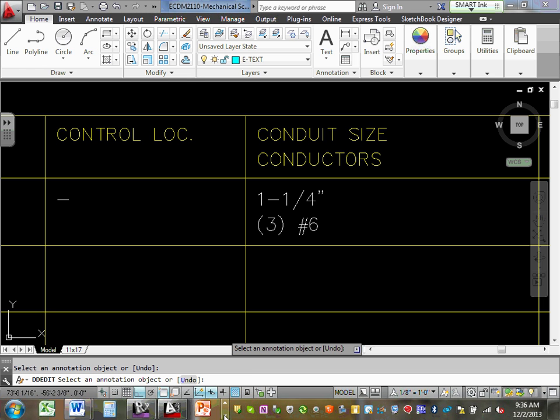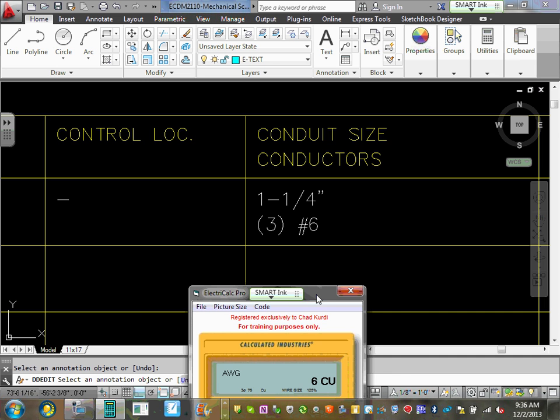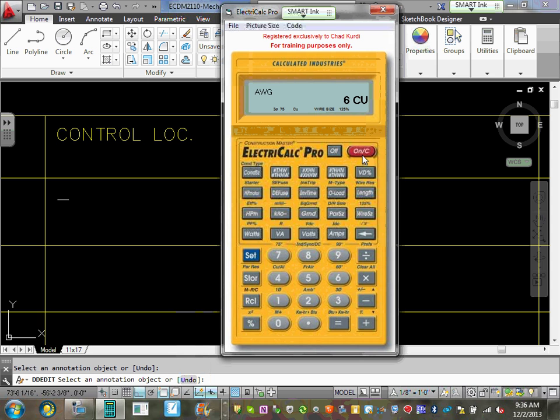Let me show you how to size the conduit. Either use the calculator, or you're going to go back to how we sized conduit before. Now remember, this is indoor, number 6. How to size it? So here's 6. Wire size, 6. How many of them do I need? 3. For the air handling unit, I need 3. And it's indoor, so it's going to be THHN. So 3 conductors THHN. Here's what you get. And then conduit size, EMT is going to be 75.